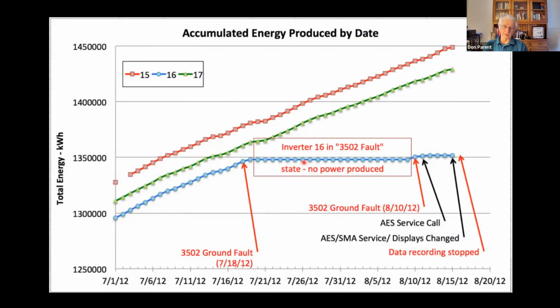In other words, the inverter was recording errors. It didn't document what those errors were, but it saturated the error count up to, I think the maximum was 256 errors. So it saturated that error count every single day during this period. And then in August, there was another ground fault that occurred, and another 3502 ground fault.